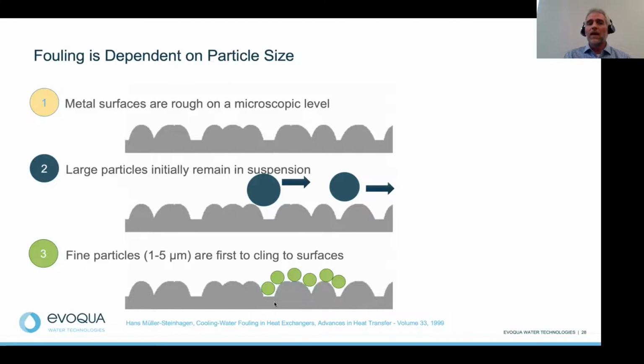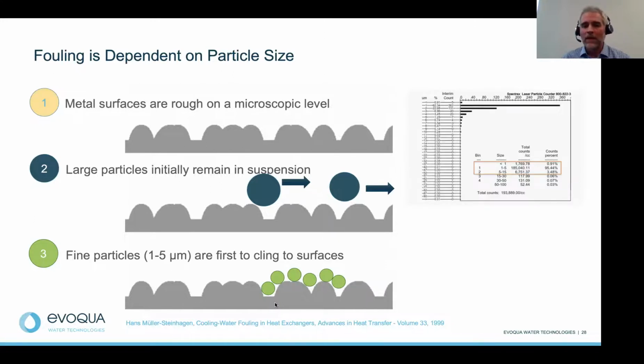But if you look at a heat transfer surface or various different surfaces in a cooling system, a lot of those surfaces are metallic in nature, right? On a microscopic level, those metal surfaces are very rough. And when you have large particles floating in suspension, those ultimately will not initially detach. They'll continue to float in suspension and potentially drop out in the tower or in the basin. But those very fine particles, the 1 to 5 micron, are really the first to cling to surfaces and start to aid in the fouling process. Now, those fine particles start to create a fouling layer.